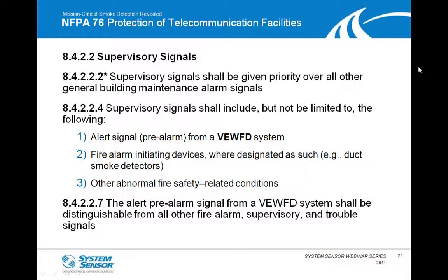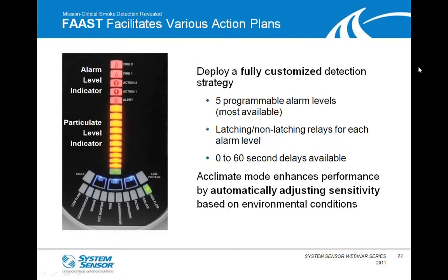And then in 8.4.2.2, the alert pre-alarm signal from this very early warning fire detection system shall be distinguishable from all other fire alarm, supervisory, and trouble signals. So what does FAAST have that can help with these pre-alarms and various types of action plans that you need to put into place, depending on whether it's a pre-alarm or a real alarm?